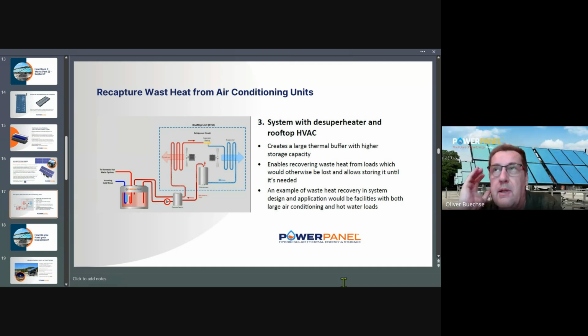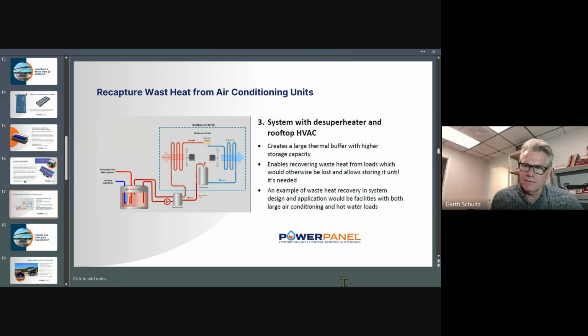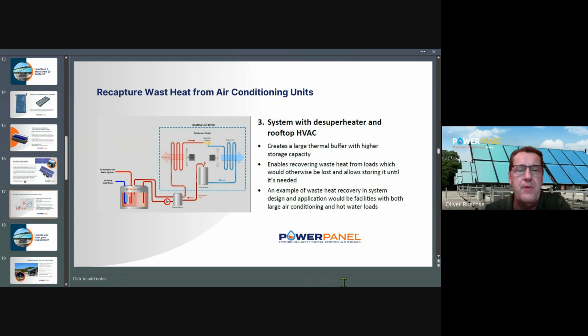So the idea is, if you have a large air conditioning unit—say on the roof or next to your building—cooling the inside of your buildings, it's basically taking that extra heat and blowing it out into the air. With this desuperheater, we can take a portion of that waste energy and turn it into hot water—basically free hot water. Is that correct? It couldn't be better than the word free. Of course, you have to pay for the investment in the device, but the operating cost is essentially free.